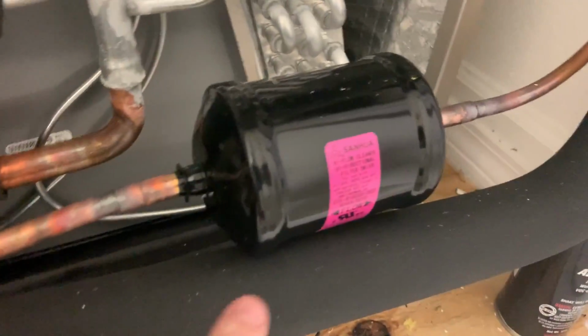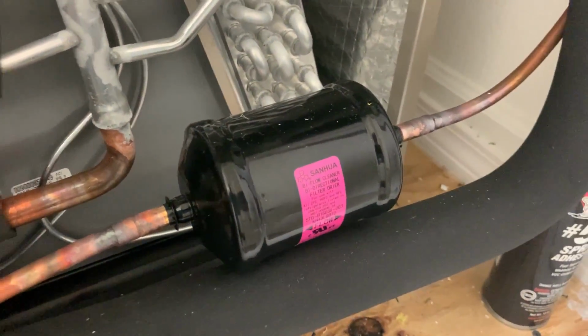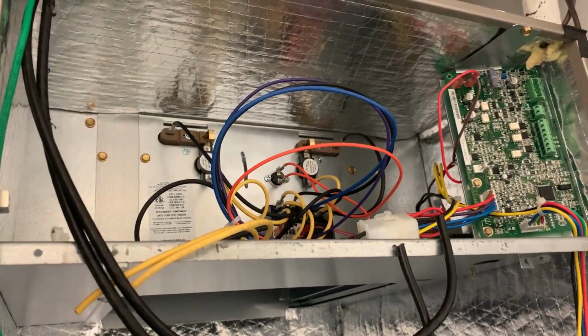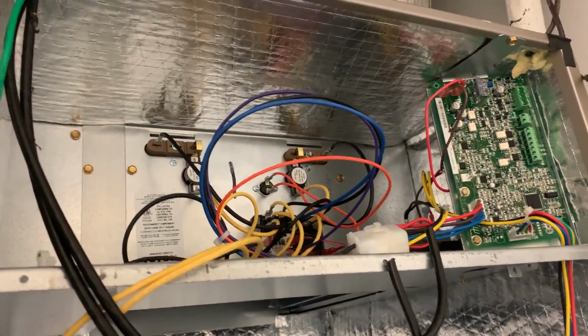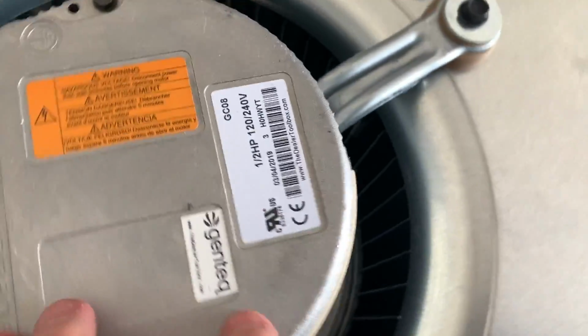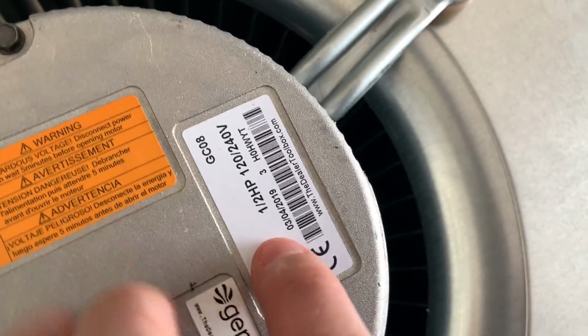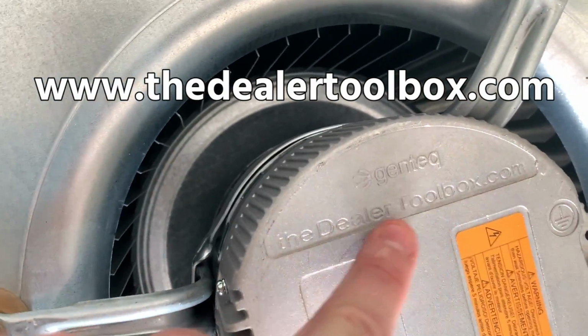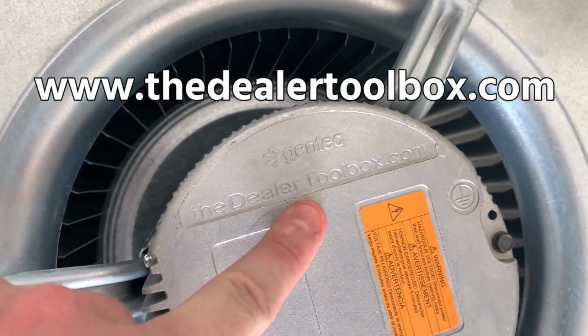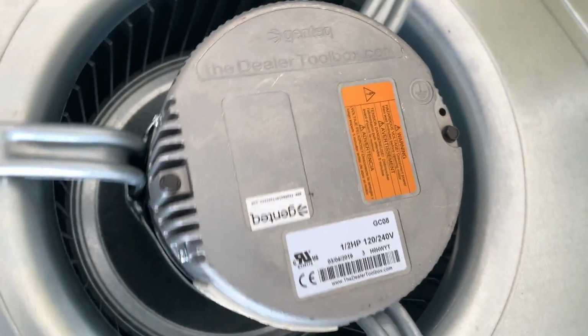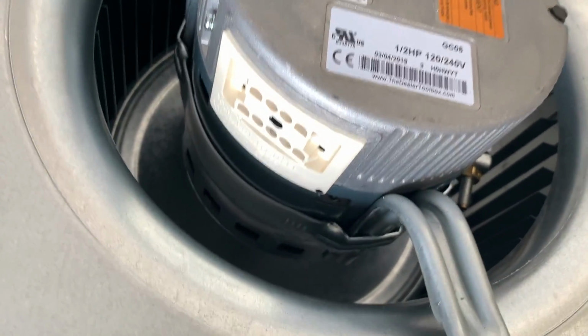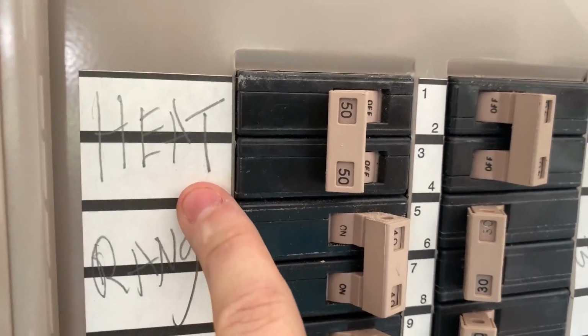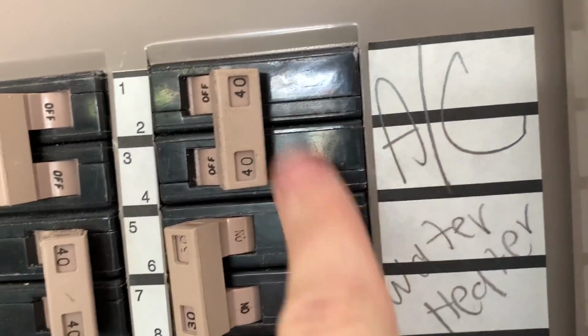There's the mastic lines, nice and clean. And the line dryer indoors to protect it from the elements. Looks like we got 10 kilowatt heaters on this. Oh no, actually 7.2 kilowatt. There's your blower motor, Genteq. If you've never gone to the dealertoolbox.com, it's a great resource for diagnosing ECM motors, either X13, ECM 3.0, 2.0, whatever you got. 50 amp on the air handler, heat strips, and we got a 40 on the outside condenser.